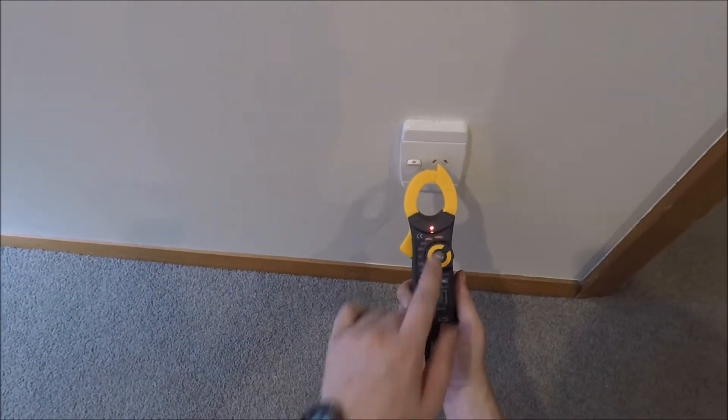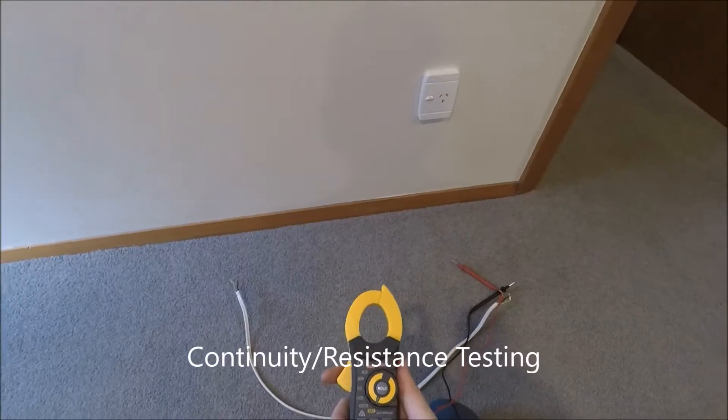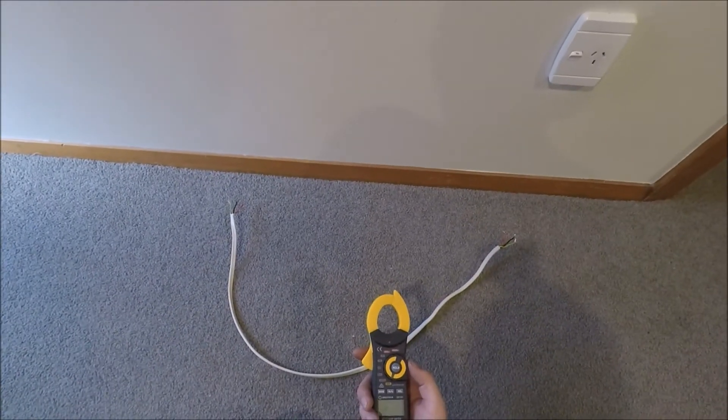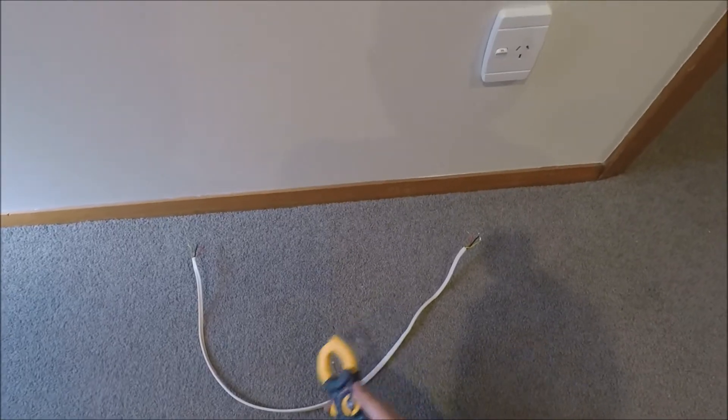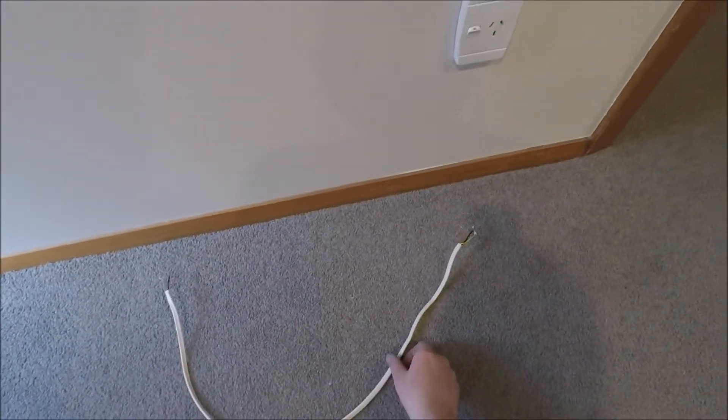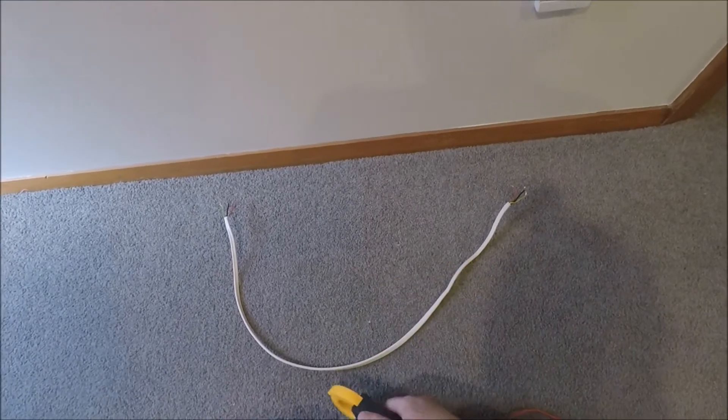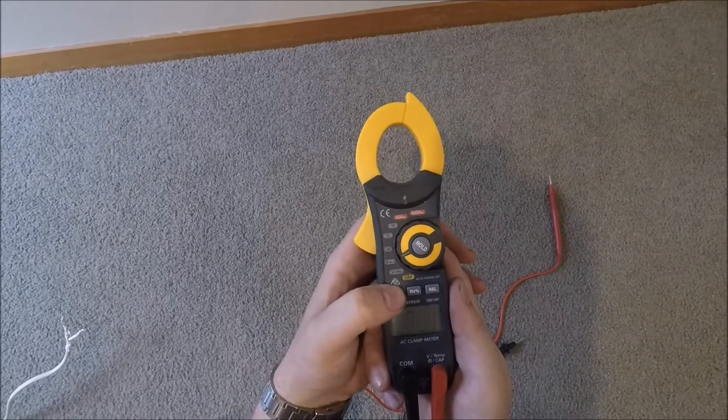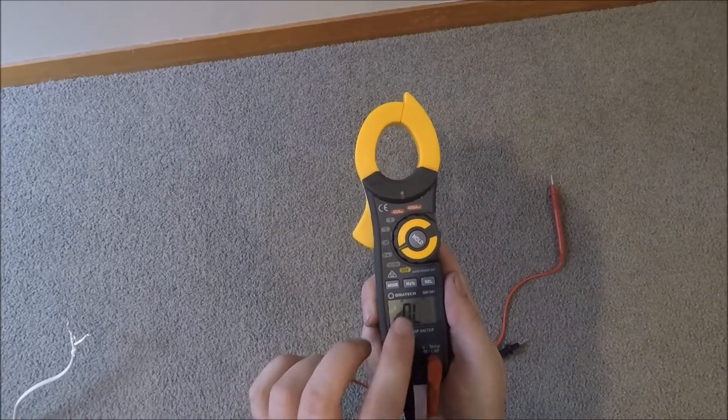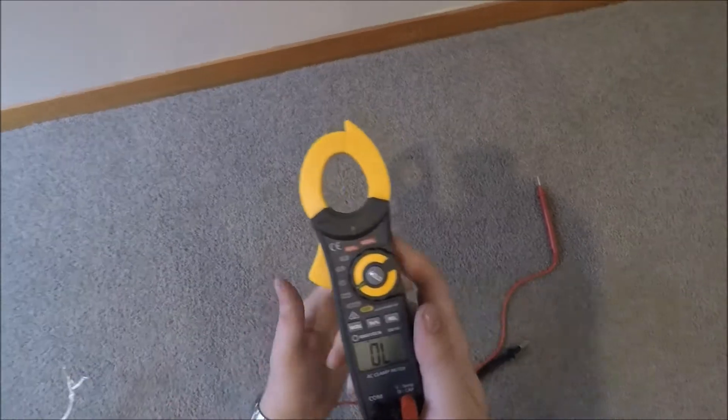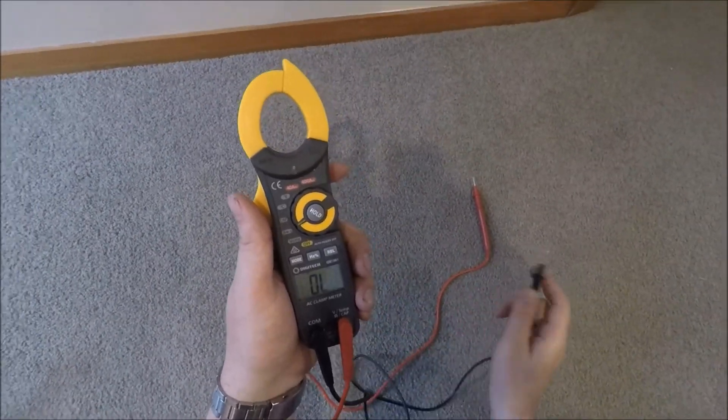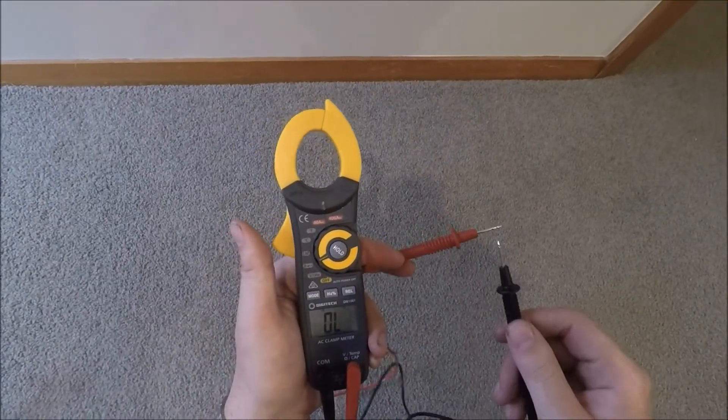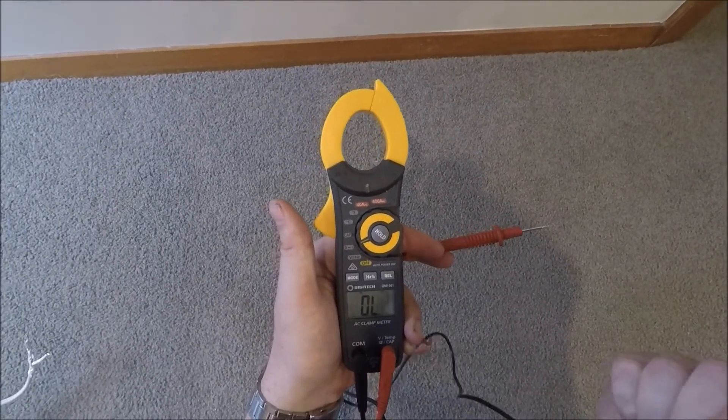I'm going to quickly run through continuity. What we use continuity for is finding cables that we don't know where they go, and we can trace them anywhere, providing the cable goes back through other power points or through the switchboard. If we put it on ohms, just the mode button on here, it'll have that little sound icon. That means now when it picks up continuity, when a circuit is closed or complete, it'll make a beep.